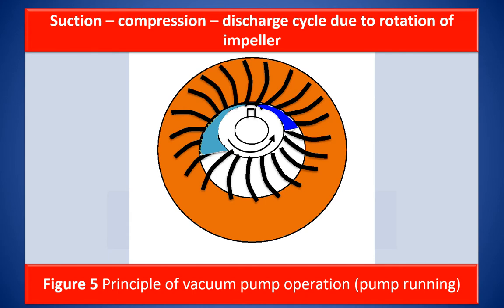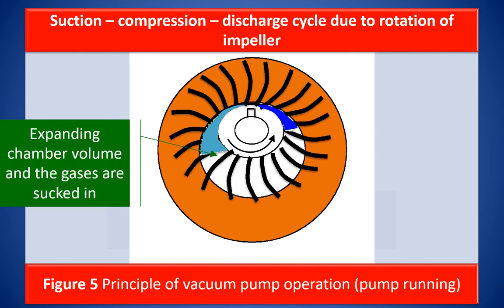The volume of the small chamber gradually increases from small to large as the impeller rotates and the pressure decreases. When the impeller reaches the suction port, the pressure has reduced to just below the pressure in the suction vessel and the gas starts flowing into the cavities or cells through the suction port. When the suction is completed, the cell is isolated from the suction port.